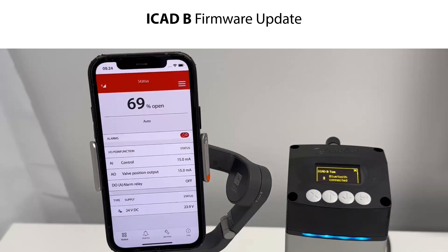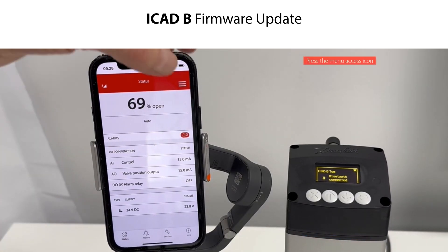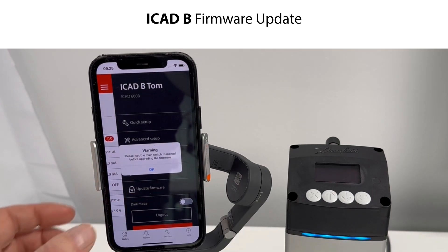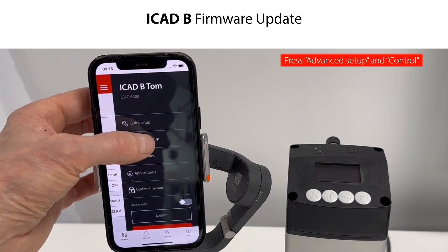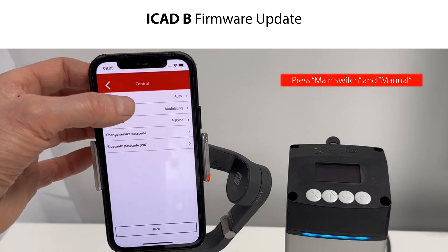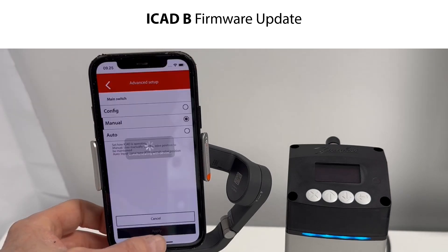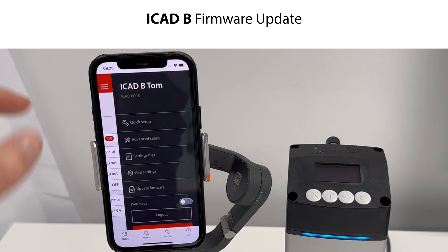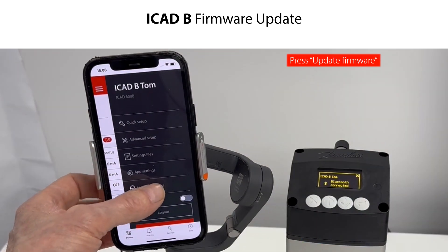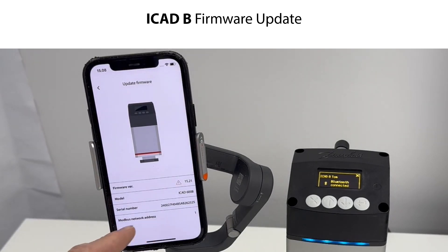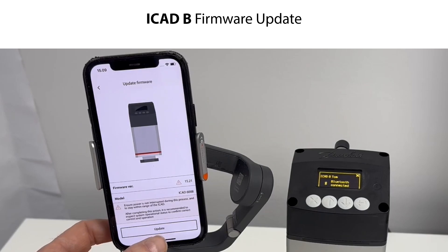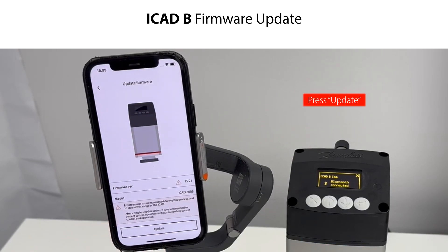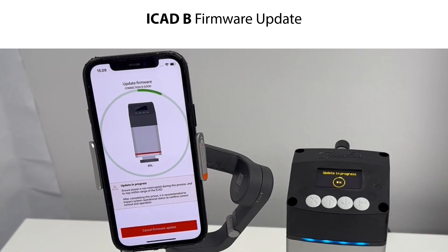Let us now do a firmware update of the ICAD-B using the smartphone app. Press the menu access icon and press Update Firmware. You first need to set the main switch to Manual before doing a firmware update — press OK to this. Press Advanced Setup, press Control, then press Main Switch and press Manual. Press Apply to set the ICAD-B to manual operation, then press the back arrow several times to return to the setting menus. Press Update Firmware. In this example, firmware version 14.0 is installed and the newest available version is 15.21. Press OK to confirm and press Update to do the firmware update. The update starts and is identified on both the smartphone app and the ICAD-B display.